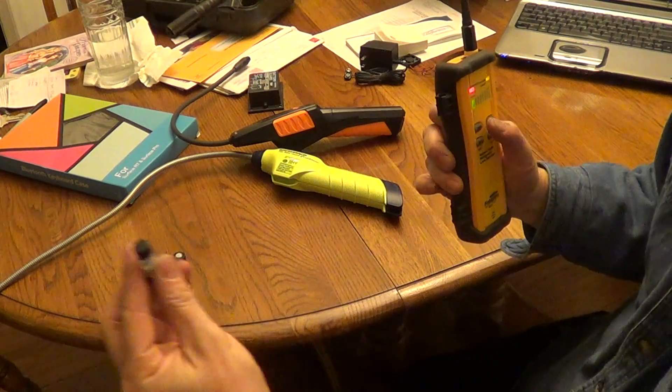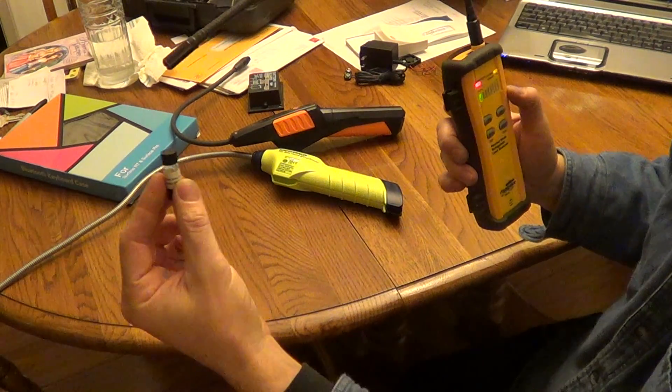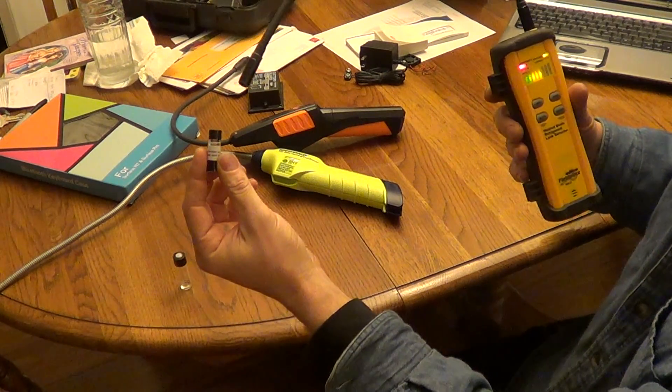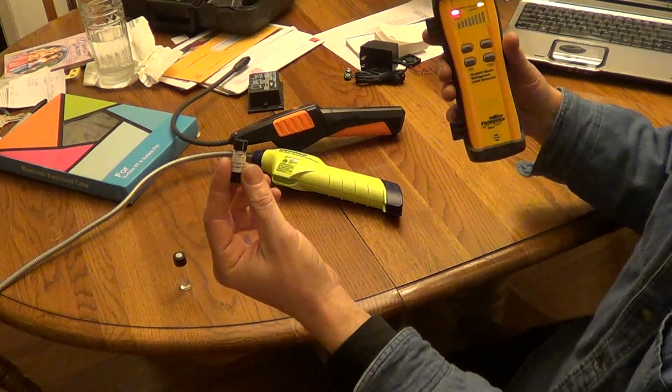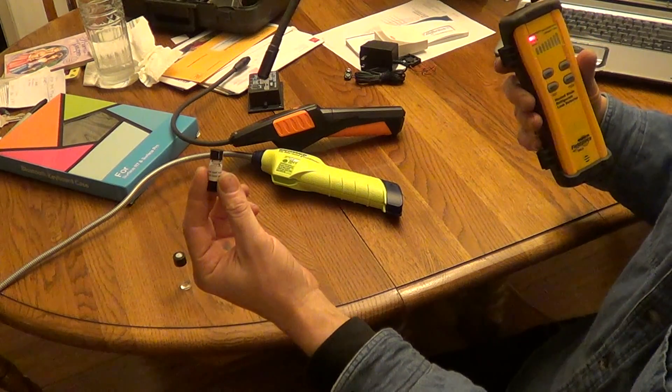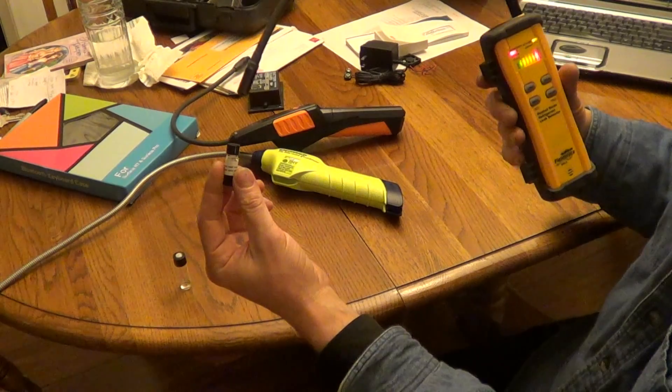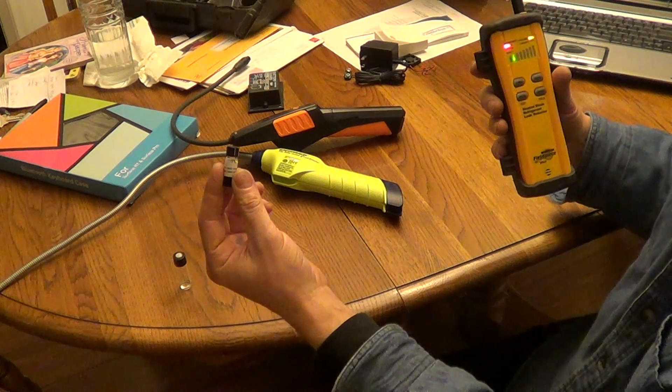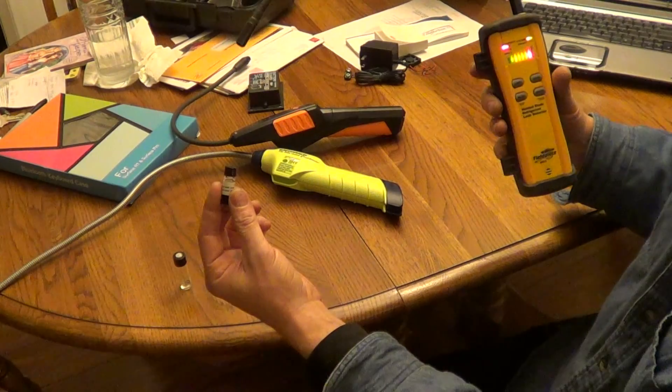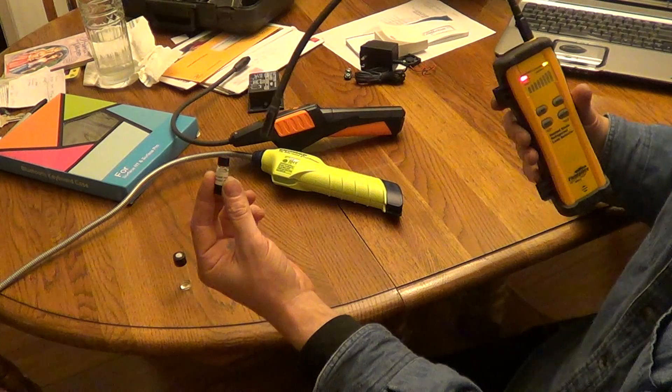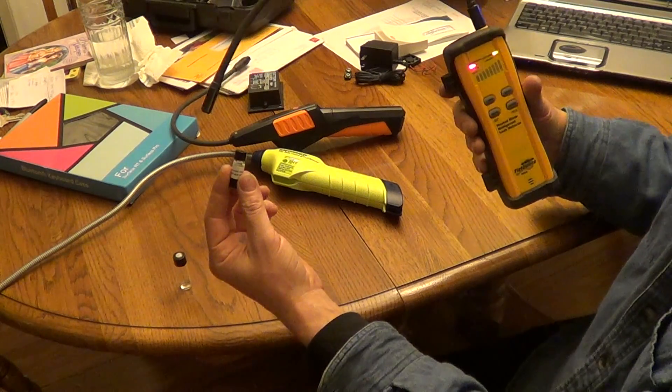Okay, the Fieldpiece on the fluorine, the HFCs, extremely sensitive. I mean literally picks it up inches away. Depends which way the wind blows. Easily picks it up maybe two inches away, or just right in the right spot.